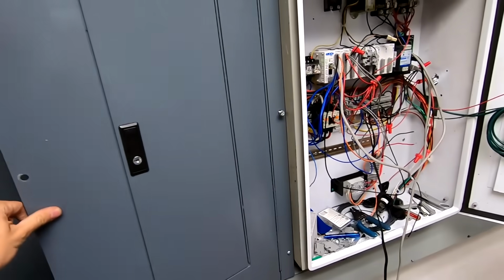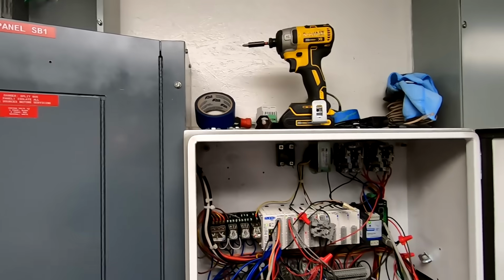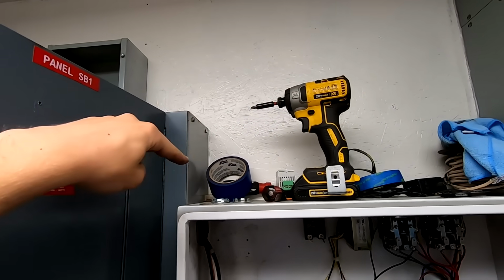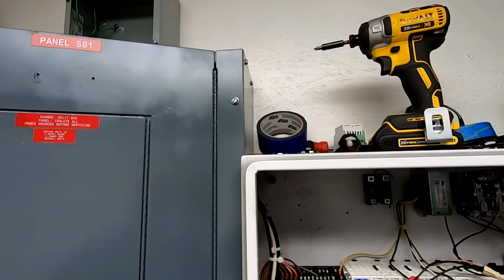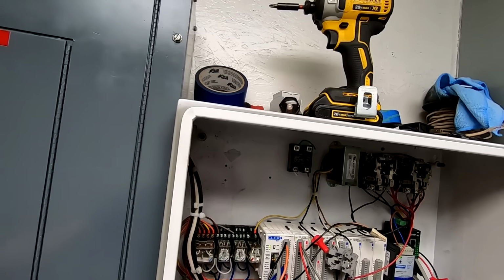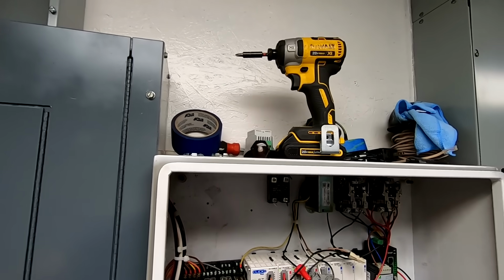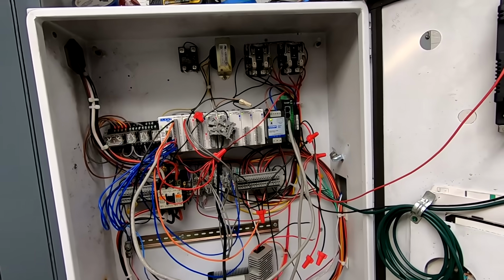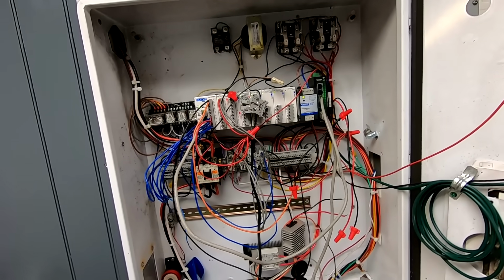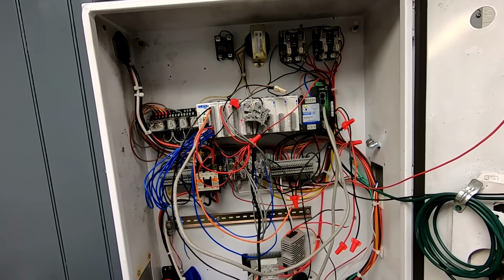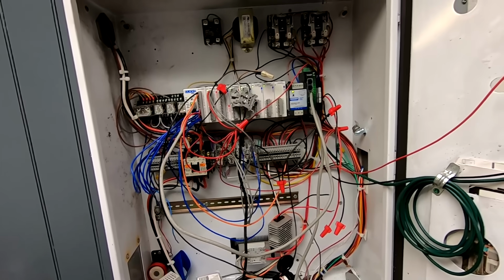And then what I will likely do is just bend up a little piece of half inch EMT to come down around this corner, and I'll use that EMT for control lines and voltage sensing. That way the PLC can verify that the contactor is actually closed and verify the generator voltage. So that's some of my plans.